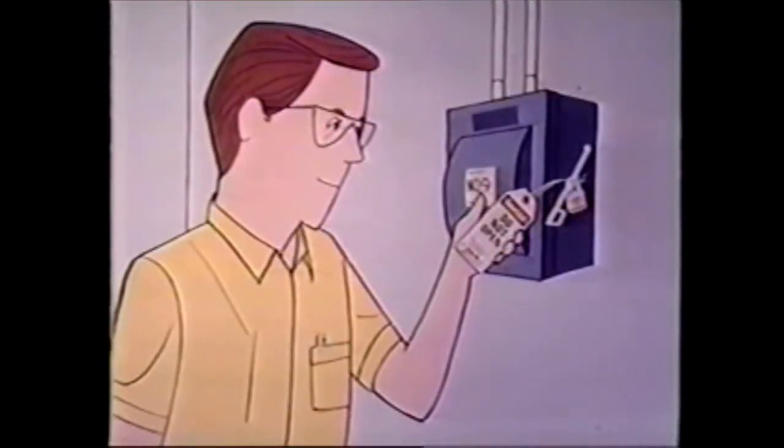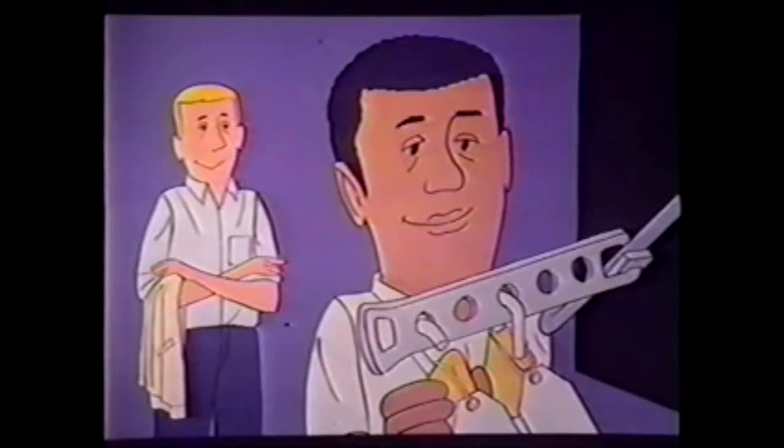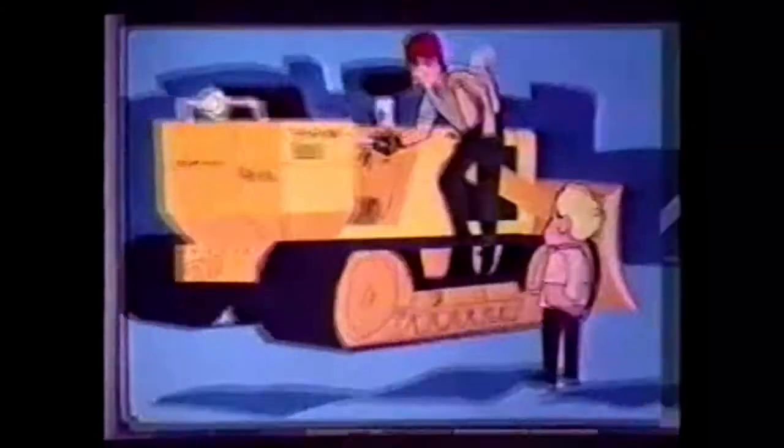The supervisor should be responsible for properly executed departmental lockouts and the adequacy of the lockout procedure. When changing shifts, the relief person will attach his or her lock prior to the relieved person's lock being removed. The disconnect will always be protected during the procedure.